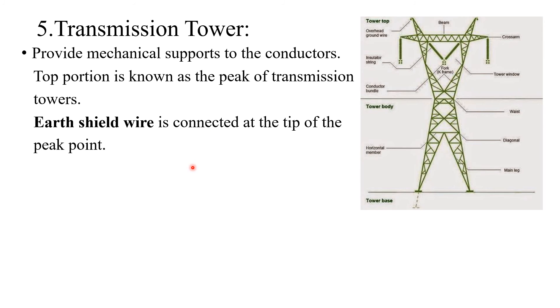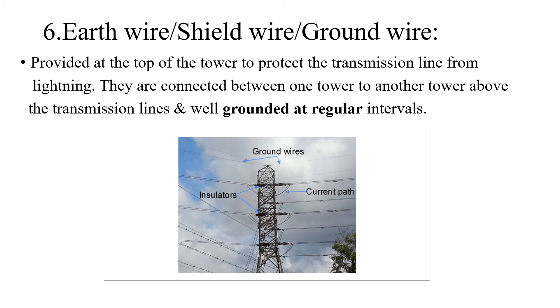The fifth important component is the transmission tower. They provide mechanical support to the conductors. The top portion of the transmission tower is called the peak. An earth shield wire, or simply earth wire, is provided at the top of the transmission tower. Earth wires are provided at the top of the transmission towers to protect the transmission line from lightning and are connected from one tower to another above the transmission lines, and well grounded at regular intervals.